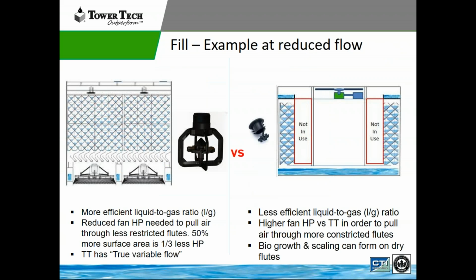However, when we drop this down to 50% flow, this is where we have our significant advantage. So at 50% flow, we're able to cover the full fill of that cooling tower and not have dry areas like traditionally happens in a cooling tower. And so we have a high liquid to gas ratio on the fill, which allows us to then run our fans at reduced speed with the VFD, which saves significant energy at part load. And most of our chiller plants are operating at part load.